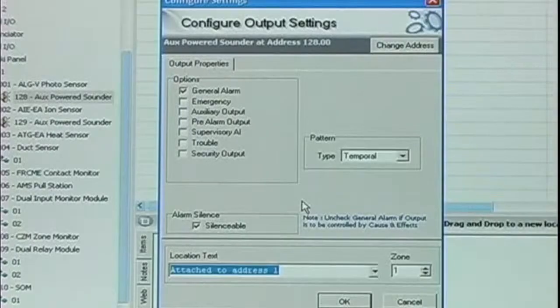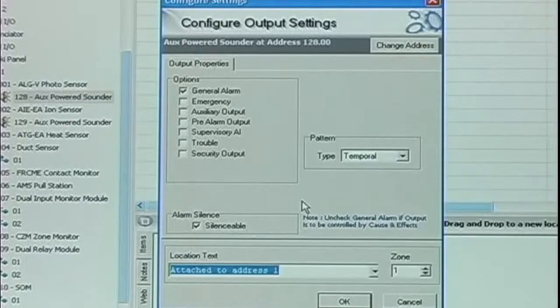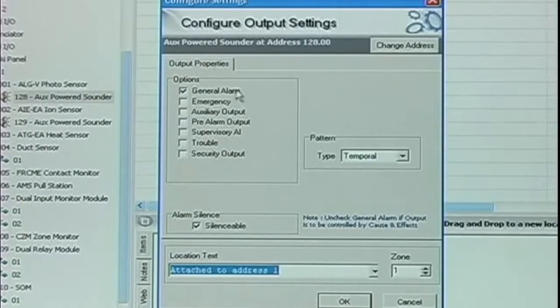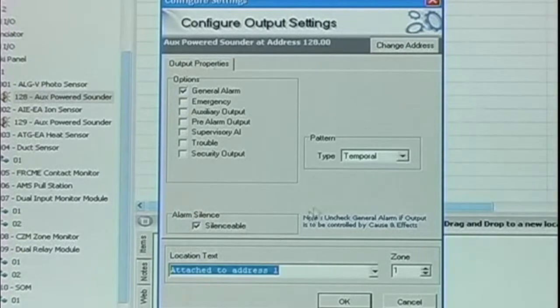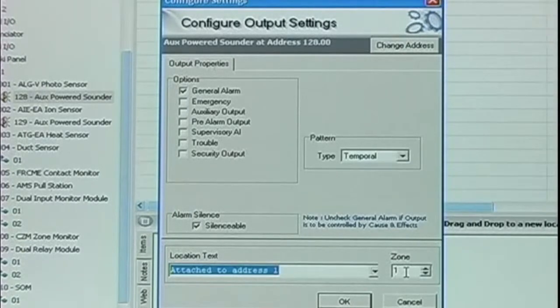Let's take a look at the settings. You'll see that the configure output settings for the ASB are very similar to the configure output settings for the SOM module. We have our general event categories, we have our output pattern, we have our silenceable option, and our location text, and our zone information.